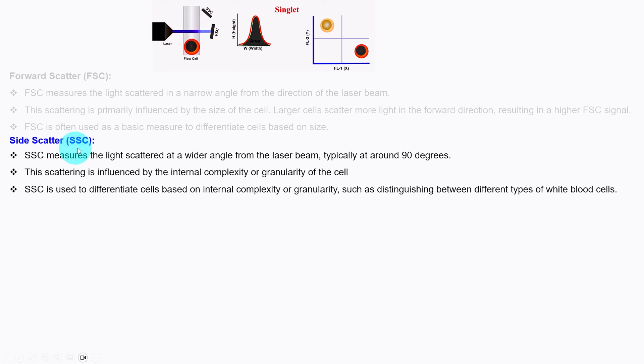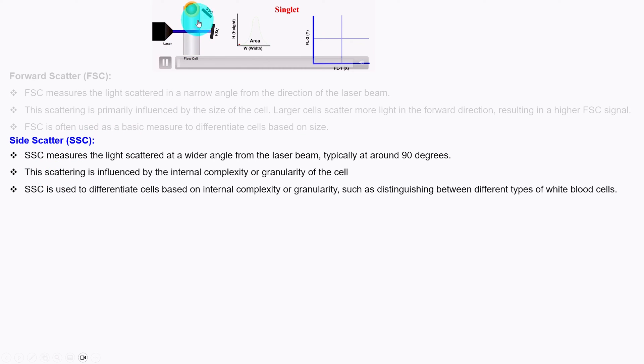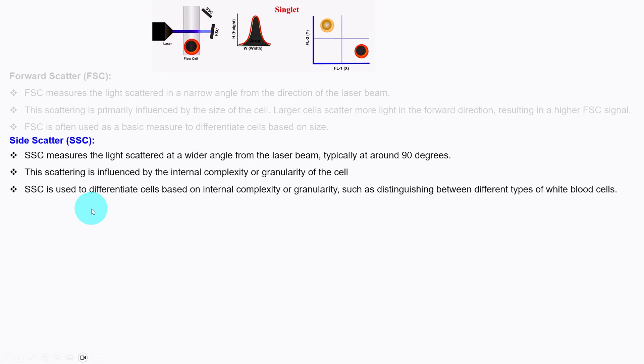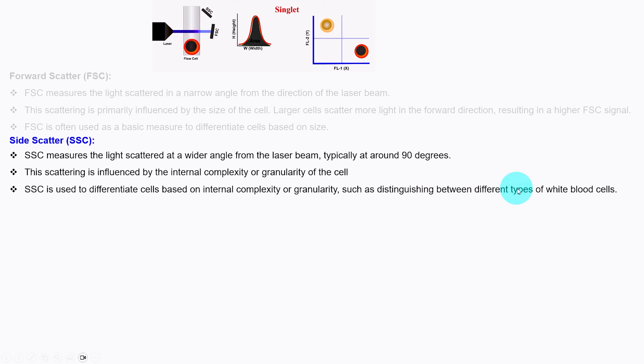Next is side scatter, SSC. SSC measures the light scattered at a wider angle from the laser beam, typically at around 90 degrees. This scattering is influenced by the internal complexity or granularity of the cell. SSC is used to differentiate cells based on internal complexity or granularity, such as distinguishing between different types of white blood cells.